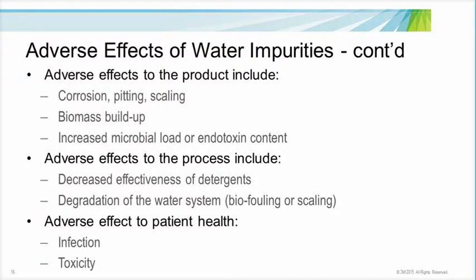Adverse effects of excessive levels of impurities may lead to product-related issues such as corrosion and pitting, or functional failures due to the buildup of organic soils, or what we refer to as biomass. If these excessive impurities are microbial in nature, the sterility of the device may be impacted or compromised due to the fact a higher product bioburden load might excessively challenge the sterilization dose or cycle time. Adverse effects of impurities may also impact the process by interfering with the effectiveness of detergents or due to scaling of washer system equipment. And finally, patient health may be impacted by infection or toxicity from improperly treated water systems.